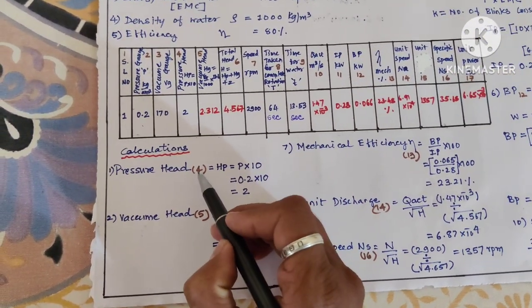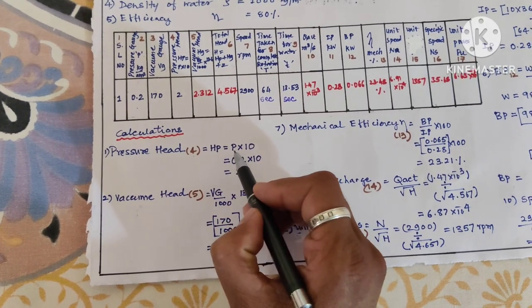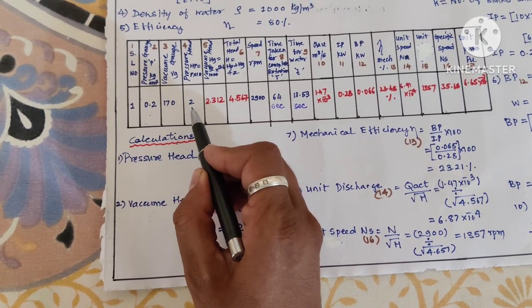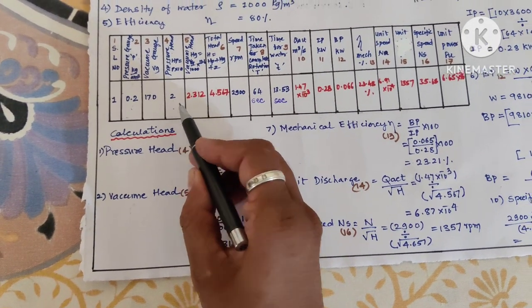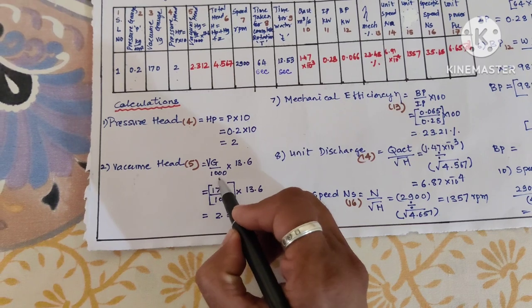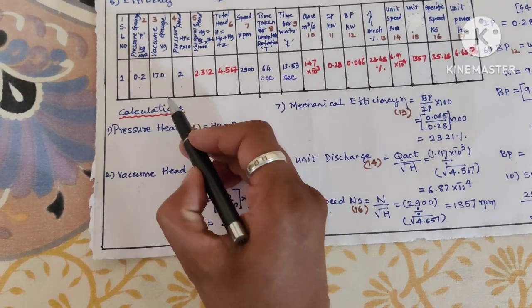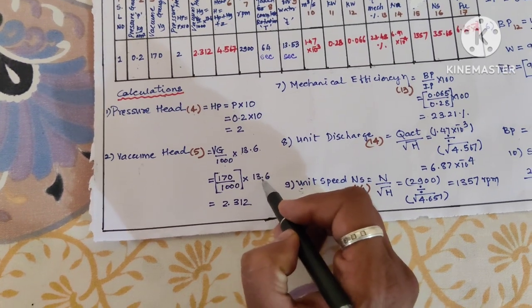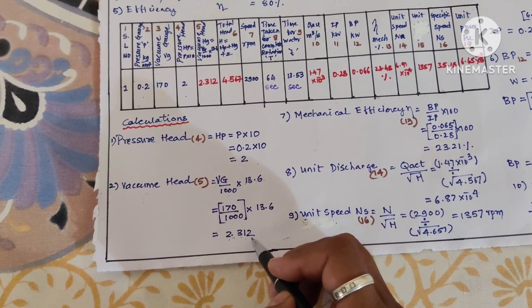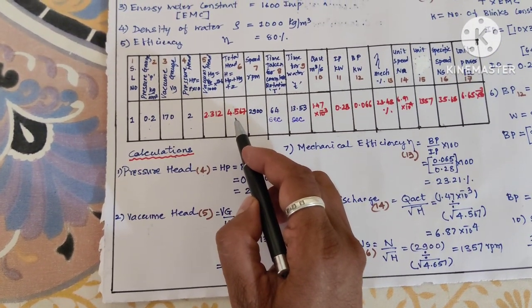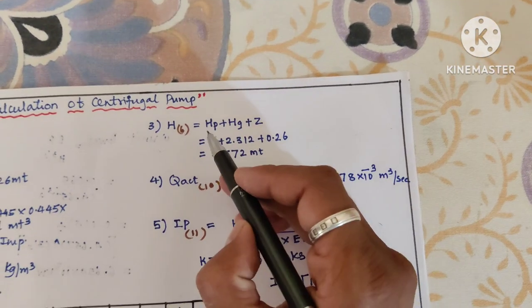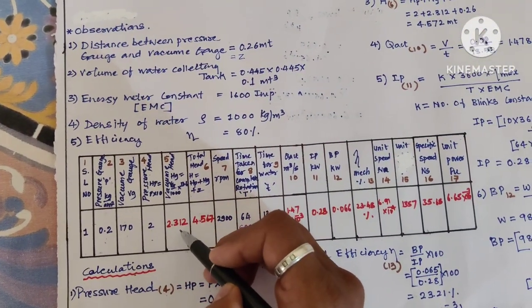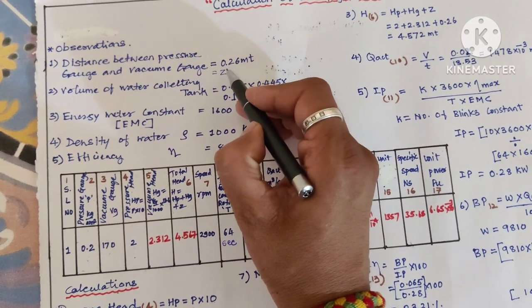Now moving to the calculations. The fourth column formula is pressure into 10, so 0.2 × 10 = 2. Next, vacuum gauge: VG/1000 × 13.6, so 170/1000 × 13.6 = 2.312. Total head: HP + HG + z, so 2 + 2.3 + 0.26 = 4.572 meter.